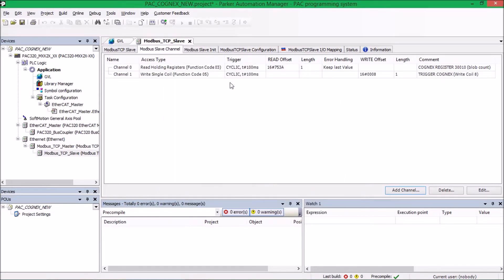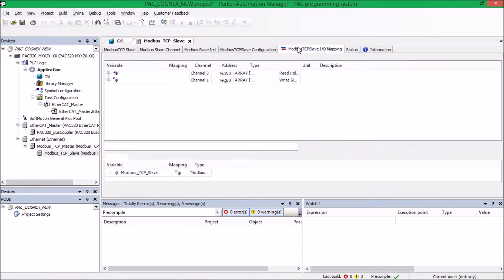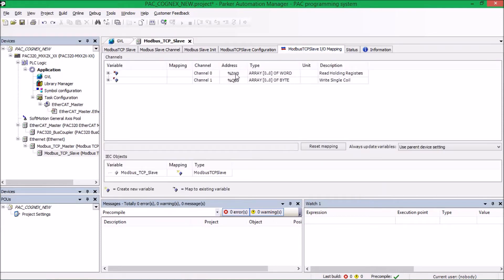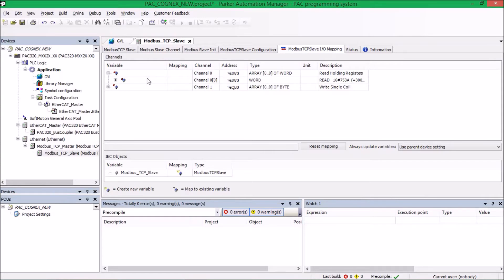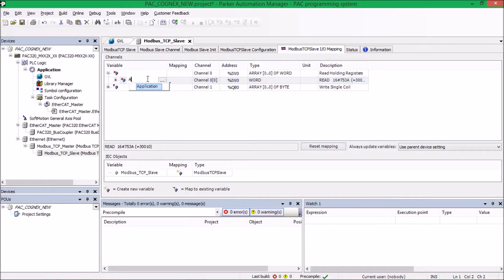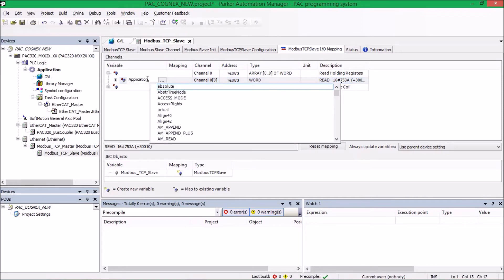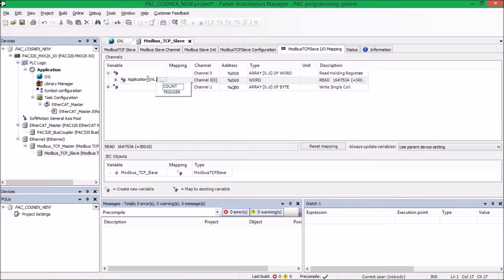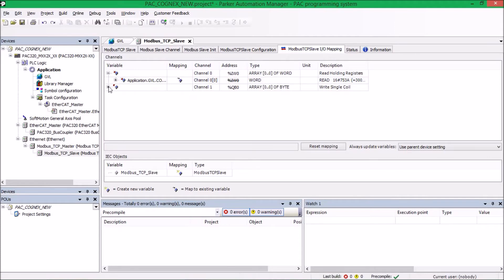And now these two channels have been added. So now I can map those global variables I created to those channels so we can see what's happening with them. We can write to them and read from them. So the word, the holding register that we're reading from, I'm going to set that equal to my count. So if I type in application, it's going to auto-populate the list. And you can see I chose GVL, which is my global variable list. And under that, I selected count.